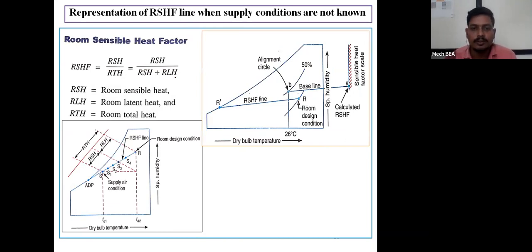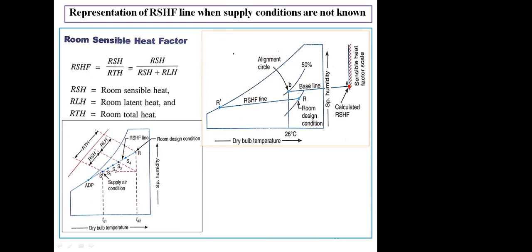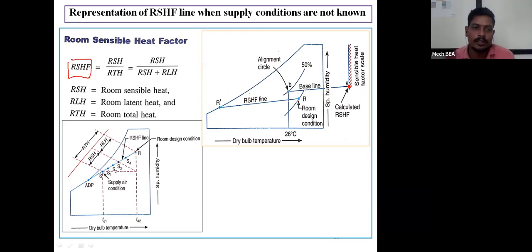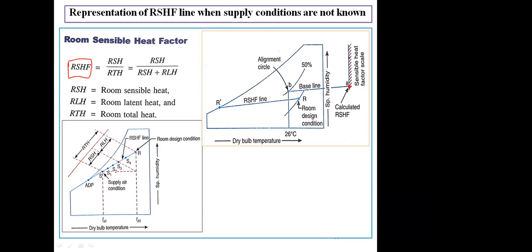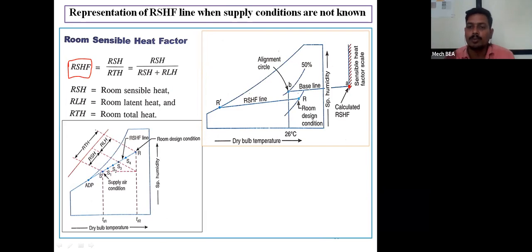There is a stepwise procedure to represent the RSHF line when the supply air condition is not known. In the first step, we calculate the room sensible heat and room latent heat, and from them the value of the room sensible heat factor. Whatever value of RSHF I get, I represent as point A on the sensible heat factor scale, which is at the right-hand topmost corner of the chart. So point A represents the RSHF calculated for the room we want to condition.